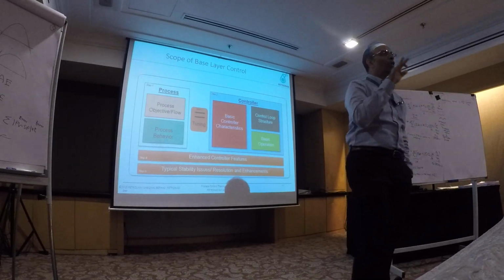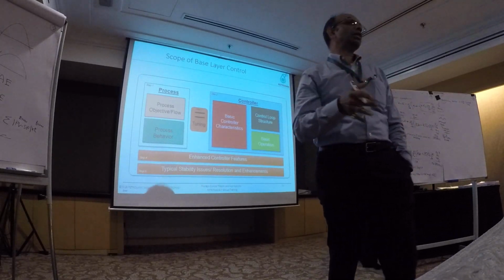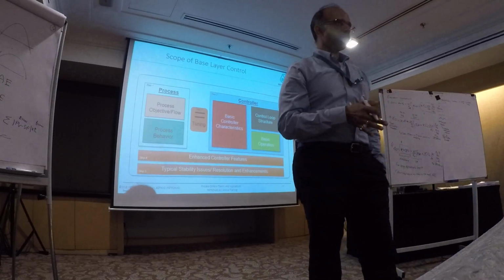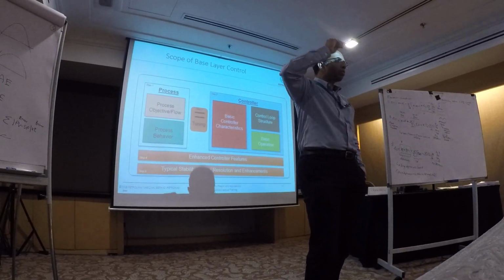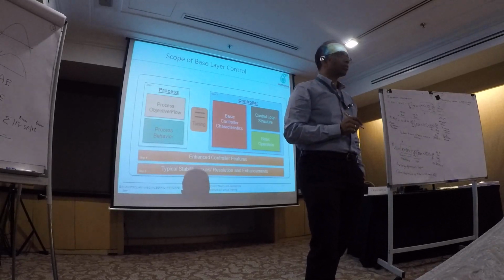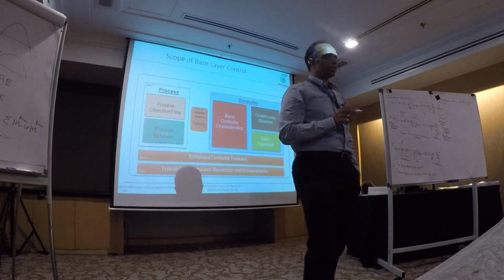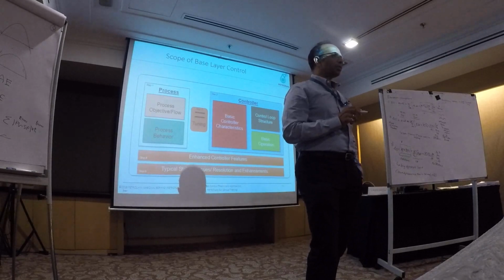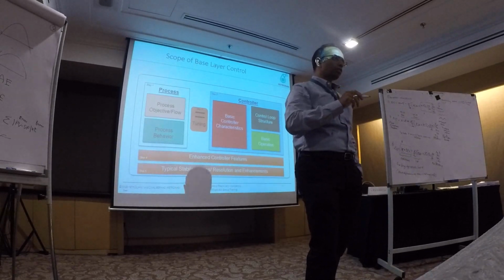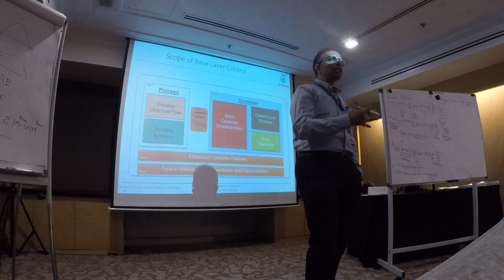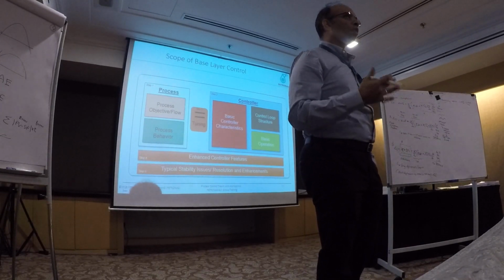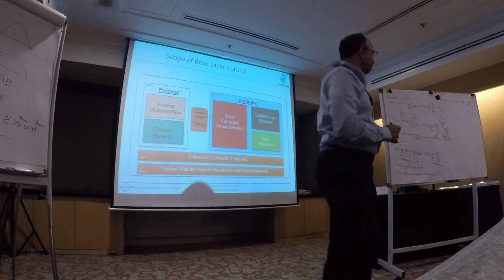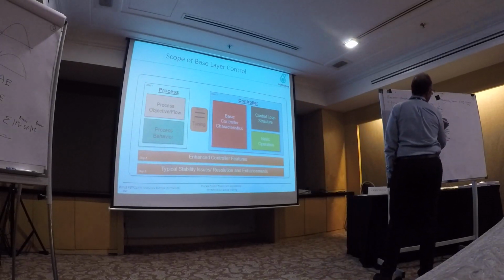And the most common one that we see is flow transmitters. Because all flow transmitters, you will always notice a little bit of shake associated. Almost all flow transmitters, especially orifice plate transmitters, you will see that. It is generated by the instrument, not by the process. What do I mean by that? Can you imagine your process doing this?